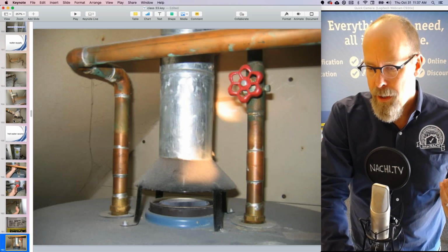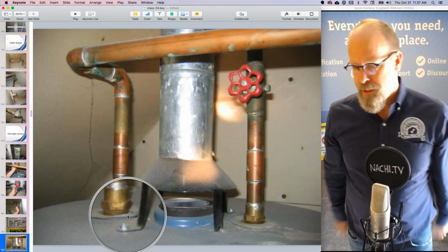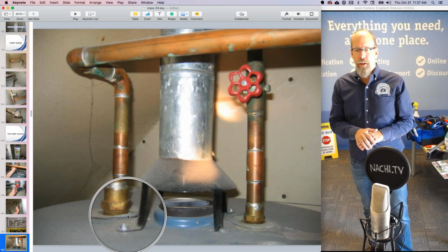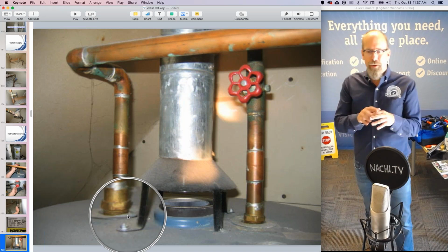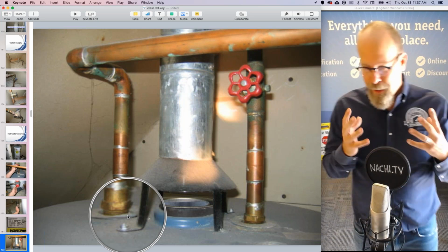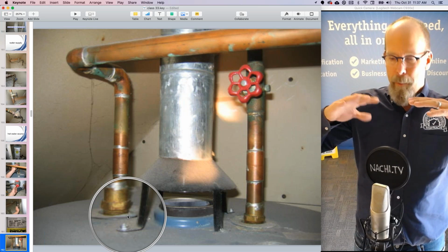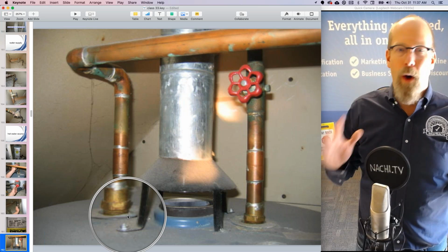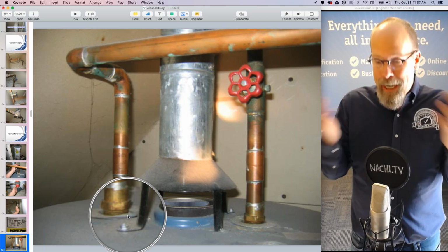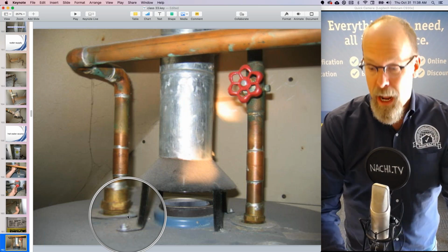Manufacturing label, natural gas right here is an indication of a backdraft of the flue. I'm not too concerned, but I'll put it in the report. That's a plastic washer. It could be removed, but it's there. It's not a functional thing, but it's melted. So that means we did have a backdraft. It was probably once, probably won't ever happen again. I don't know. It's a natural draft. So these things burp a little bit, you can explain, but I'm gonna put that in a report.